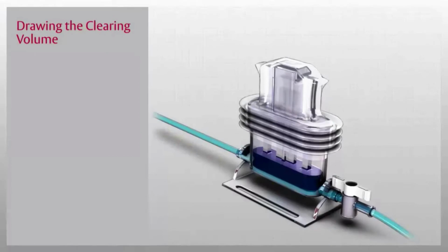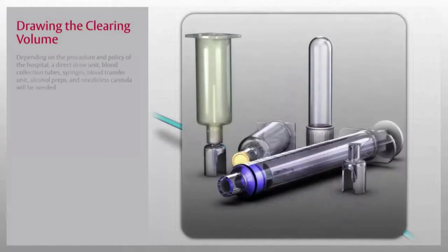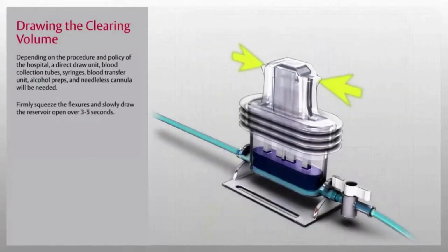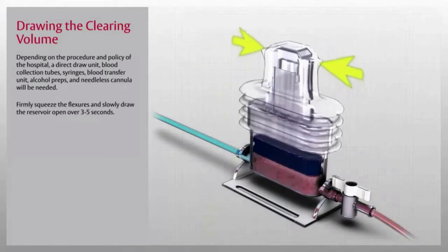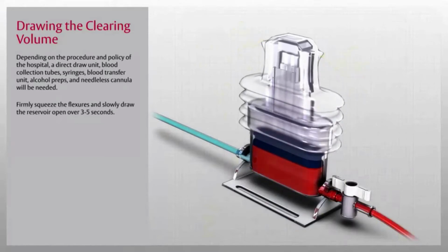Once the system is primed, you are ready to draw the clearing volume. Note: depending on the procedure and policy of the hospital, a direct draw unit, blood collection tubes, syringes, blood transfer unit, alcohol preps, and needleless cannula will be needed. First, firmly squeeze the flexures and slowly draw the reservoir open over 3 to 5 seconds. Then, close the shutoff valve by turning the handle perpendicular to the tubing. This is to prevent aspiration of blood from the reservoir.